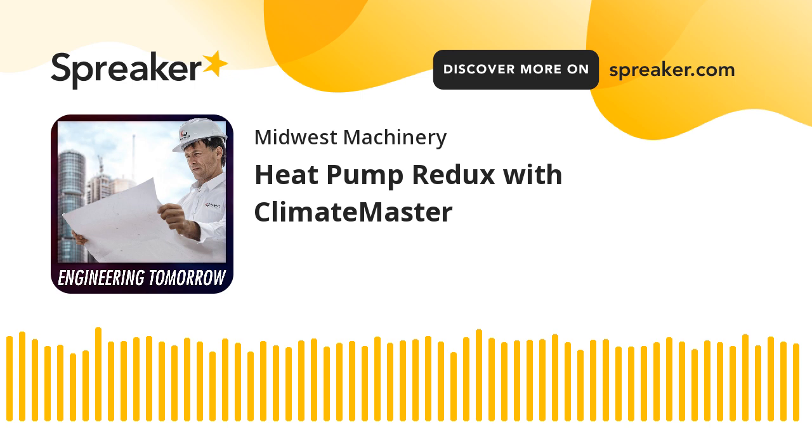The other system that we're able to simultaneously heat and cool is variable refrigerant flow, or VRF. These VRF systems are excellent at simultaneously heating and cooling. However, they shouldn't be applied to absolutely every building application. One of the advantages of water source heat pumps over a VRF system is the limited amount of refrigerant in a water source heat pump system. All of our refrigerant is contained right there in the packaged unit, in the heat pump itself. So if there's a leak, it's a small leak. It's not a lot of refrigerant. Plus, it's extremely easy to find because we know where it's at.